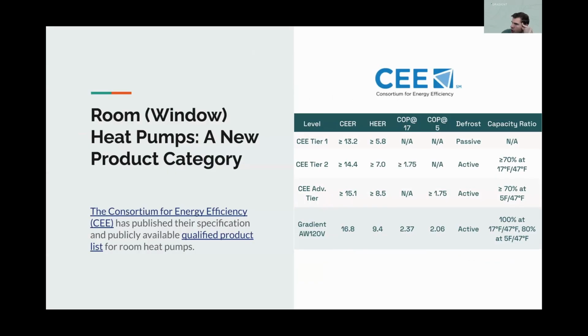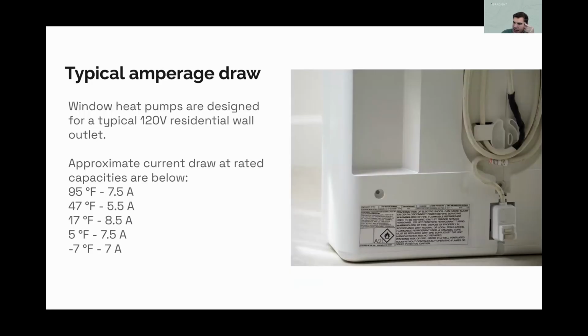The reason for that — jumping ahead to show the amperage draw of a representative system — at -7F we're pulling 7 amps, and at that test point we're still getting a COP of about 2, which means you'd need double those amps if you had resistance heat. If you double 7 amps you get 14, and you're no longer compatible with a regular outlet — you now need an electrician. You don't just need an electrician to run a 240 line to that room, you might also need to upgrade your panel to make sure the building's total amperage capacity can cover it.